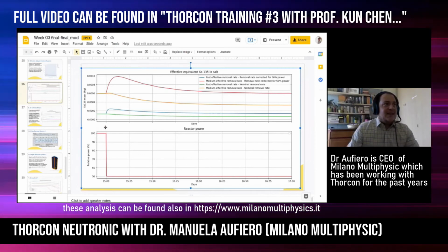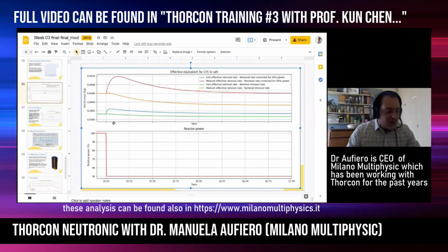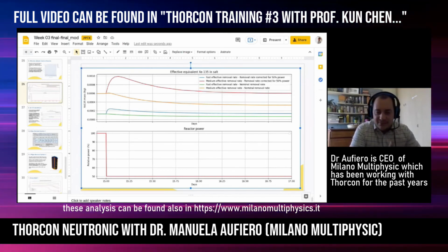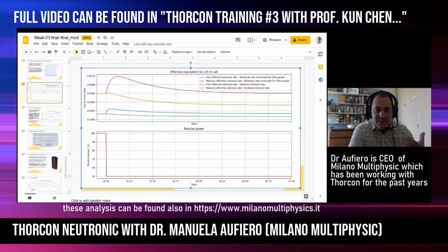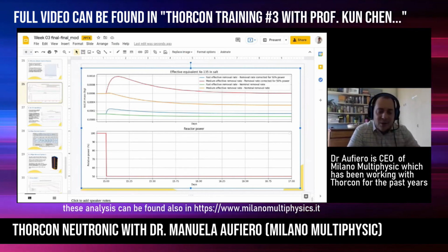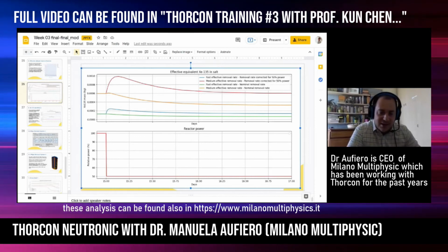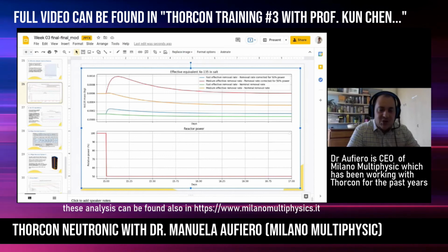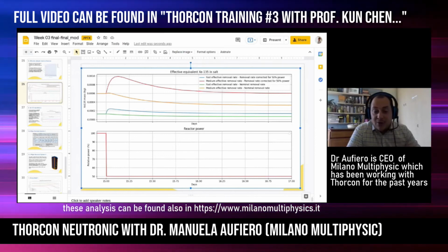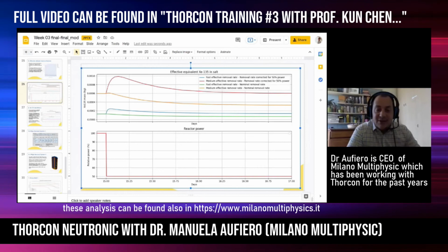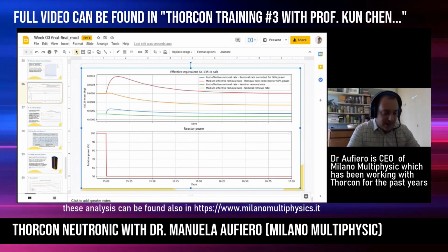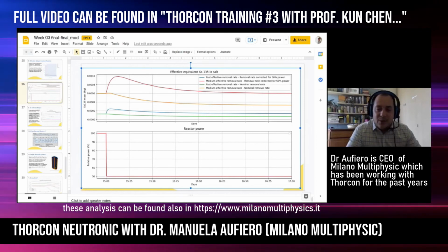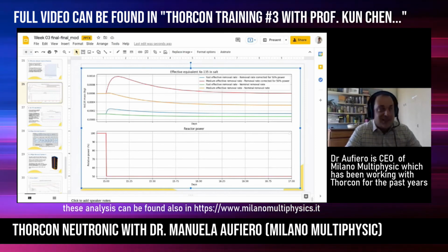In this case, the xenon in a solid fuel reactor would reach a well-known level that just depends on the amount of iodine-135 that is produced from the fission fragment and fission product decay chain, the amount of xenon-135 that is destroyed by neutron capture, and the amount of xenon-135 that naturally decays.